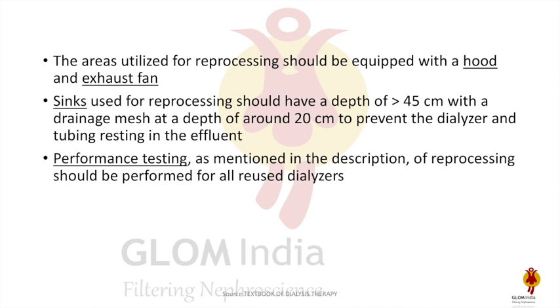The area to be utilized for reprocessing should have a hood and exhaust fan. The sink should have a depth of at least 45 cm, with a drainage mesh at a depth of around 20 cm to prevent the dialyzer and tubing from resting in the effluent.